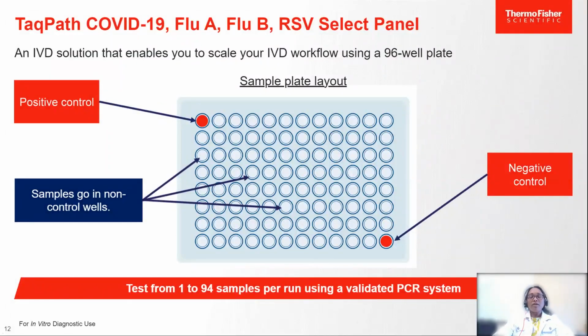All right, so here is a snapshot of what the plate looks like when you set up your reaction. Now note that this is a 96 well plate. The 96 well plate goes into the Kingfisher instrument and the subsequent PCR instrument, right? So you can set it up in 96 wells, which means that if you are allocating 1 well for positive control and 1 well for negative control, and that is a must, unless a positive control and a negative control are on each single run, the run is invalid. Right, so you have to allocate 2 wells for the controls.